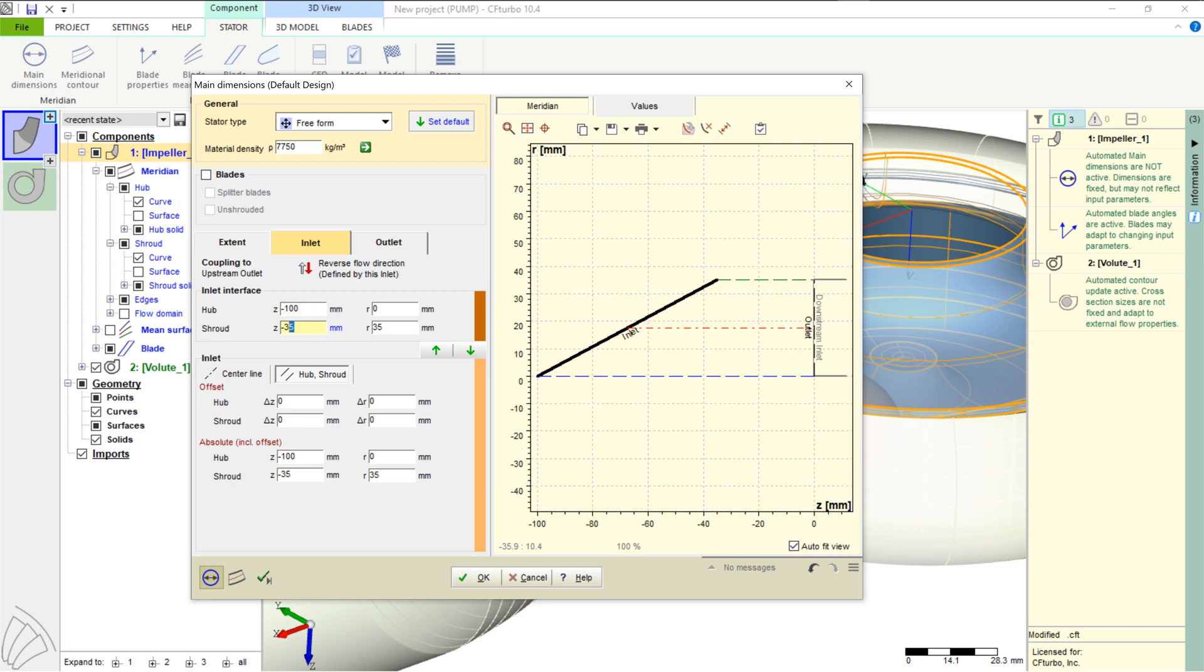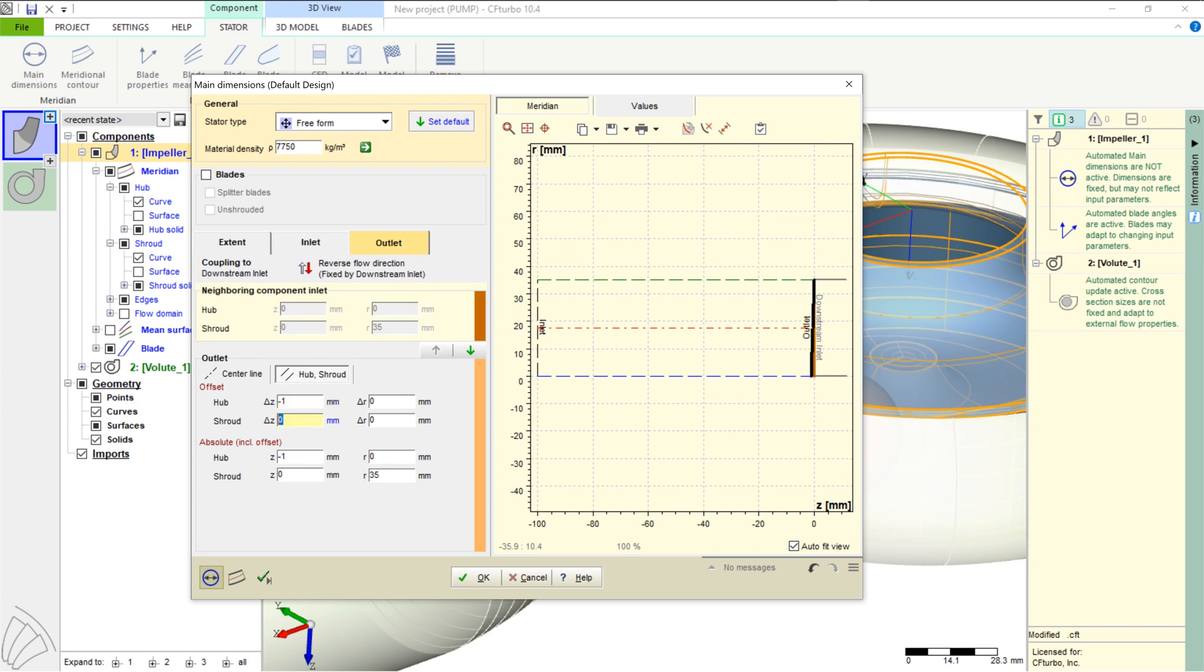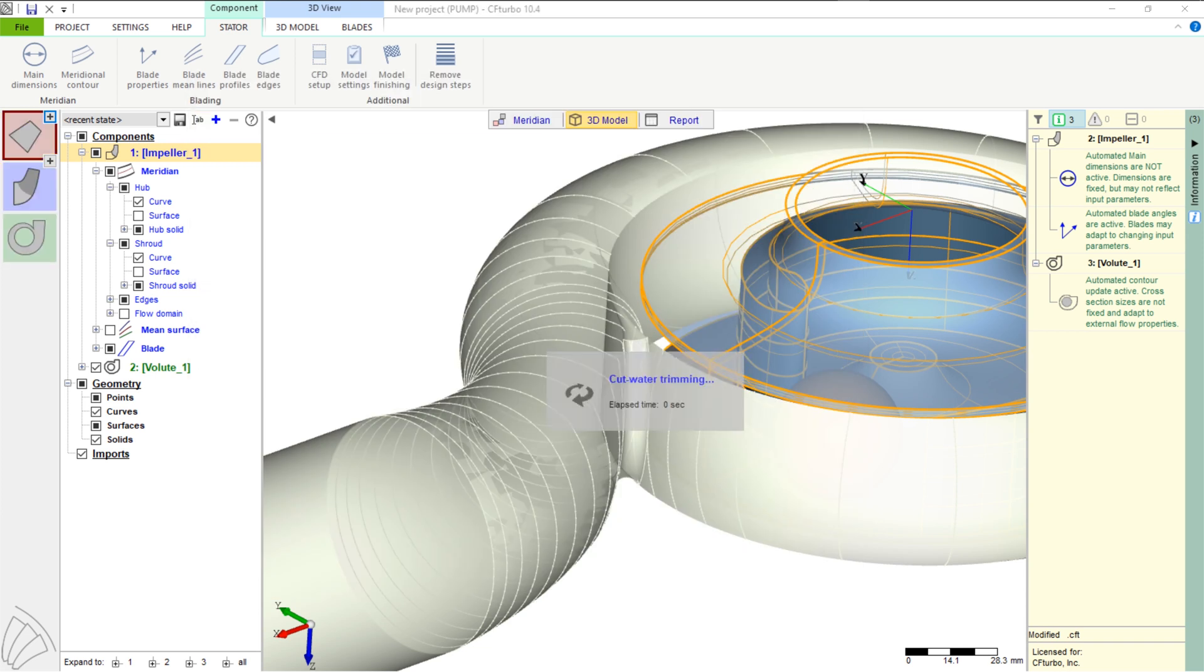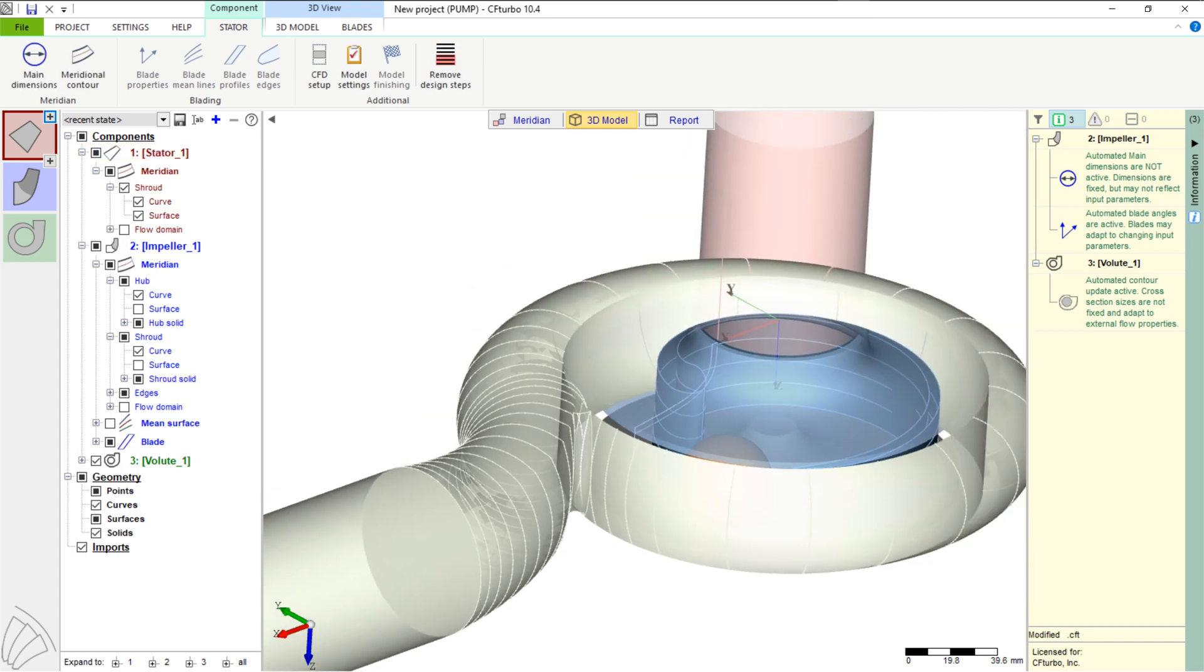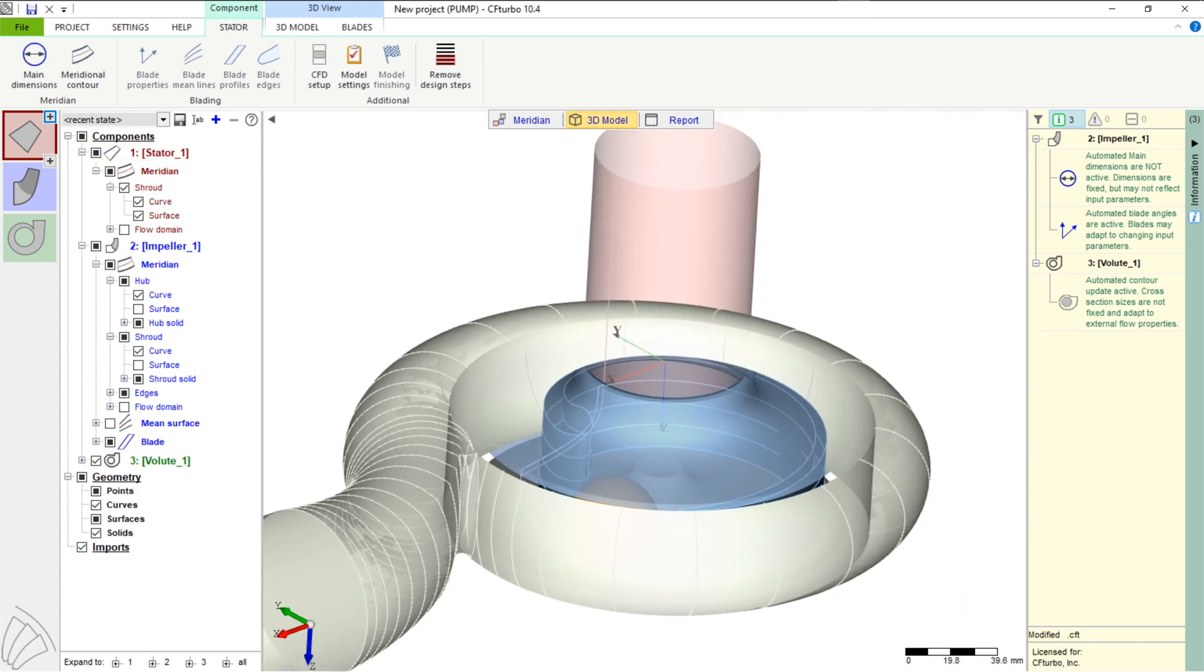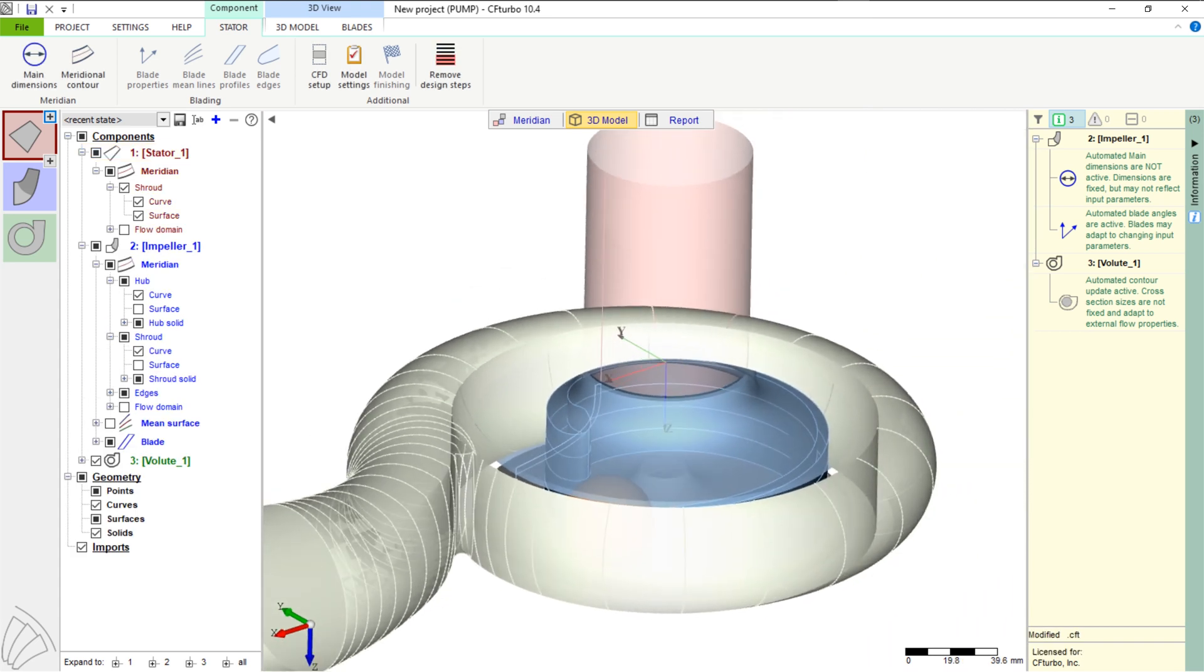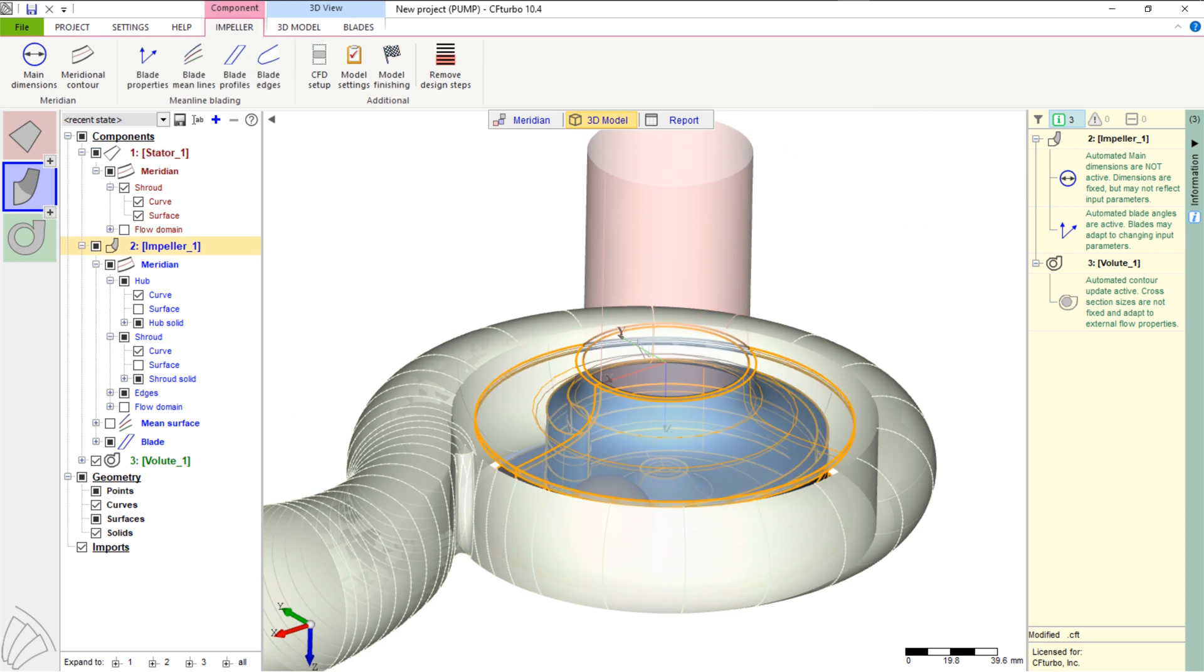In a similar way, the user should add a pipe on the suction side of the impeller. For this purpose, we add an axial stator. The stator should be given a certain length and there must be a small gap between pipe and impeller in order to create the secondary flow path later. In this case, we have added a 100mm pipe at the inlet and a 1mm gap between pipe and impeller.